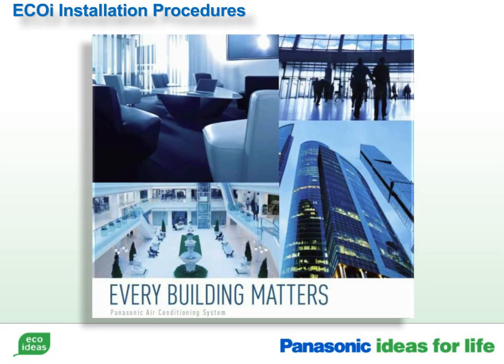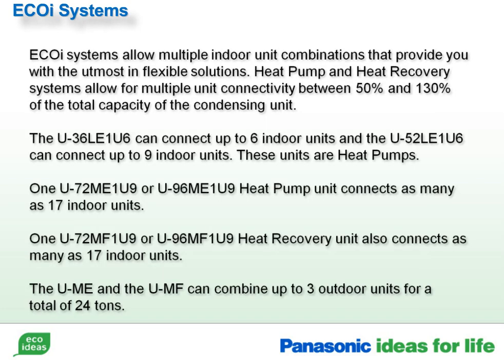This video covers the installation guidelines and procedures for the VRF heat pump and heat recovery systems. ECOi systems allow multiple indoor unit combinations that provide you with the utmost and flexible solutions. Heat pump and heat recovery systems allow for multiple unit connectivity between 50% and 130% of the total capacity of the condensing unit. The U36 LE1U6 can connect up to 6 indoor units, and the U52 LE1U6 can connect up to 9 indoor units. Both of these units are heat pumps.